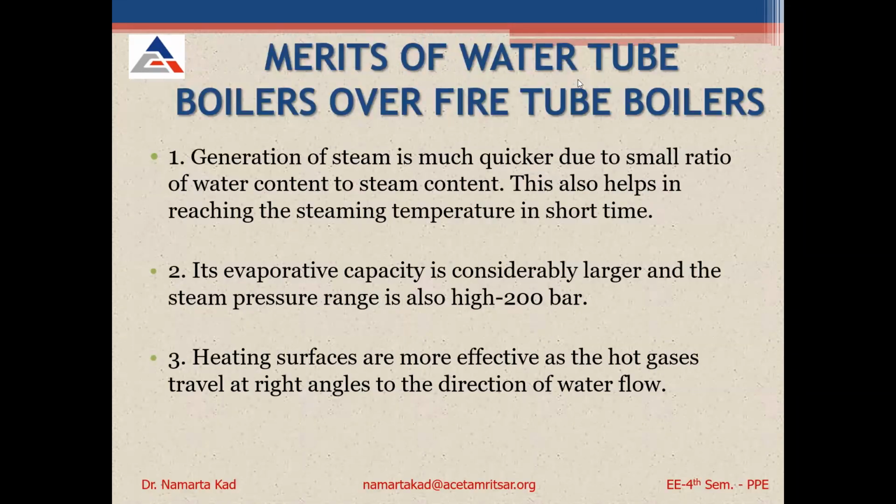Now, some of the merits of the water tube boiler over the fire tube boiler. First one is the generation of steam is much quicker due to the small ratio of water content to the steam content. Okay. This also helps in reaching the steam temperature in a short time. इसमें जो steam generate होती है ना, वो बहुत जल्दी होती है, because here the content of water is less as compared to the fire tube boilers.